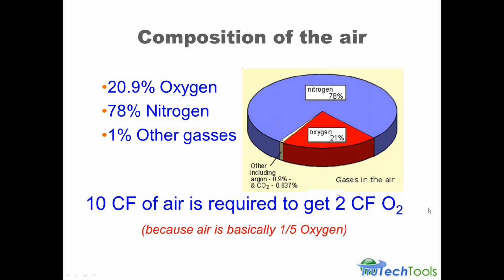So in order to get 2 cubic feet of oxygen, which may be required in a combustion process, we have to bring along 10 cubic feet of air, because only 2 of those 10, or about 1/5, is actually oxygen. And the oxygen is what is really used by the combustion system. So air is basically 1/5 oxygen, the rest of it's nitrogen, and the nitrogen comes along for the ride. We'll be talking about the impact of that shortly.